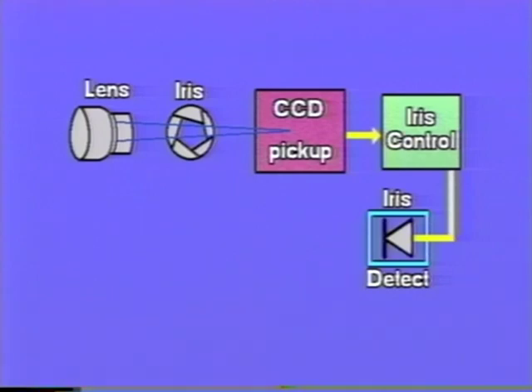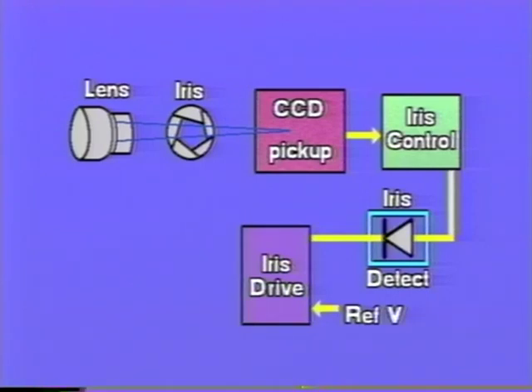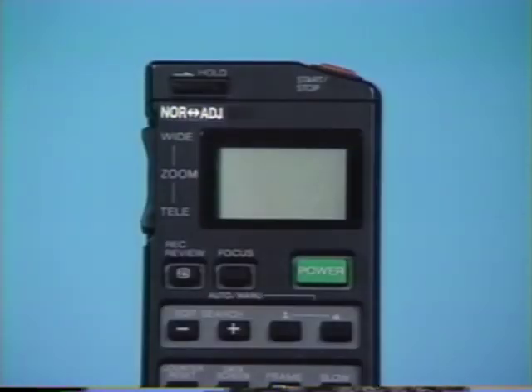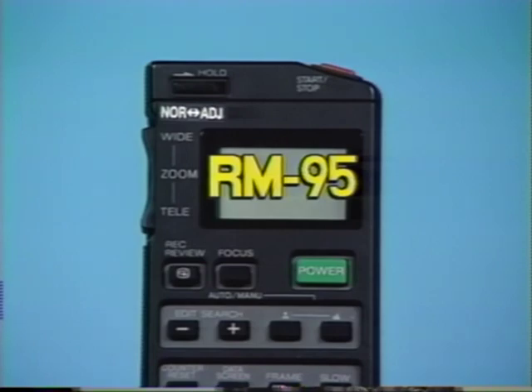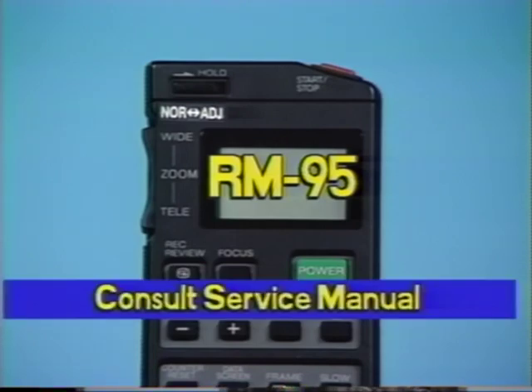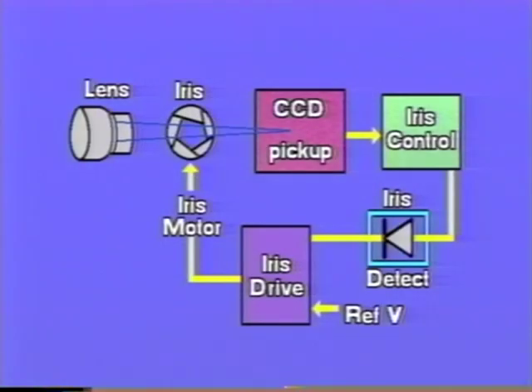The signal from the iris control circuit is sent to the iris detector where all video scene brightness levels are averaged. The resulting voltage is sent to the driver for comparison to an external reference voltage. This reference voltage is used to set the standard iris video signal level or camera sensitivity. The reference voltage can be changed using the RM95. Consult the service manual for a detailed description of this adjustment procedure. The result of this voltage comparison is used to drive the iris motor and control the mechanical aperture of the iris.